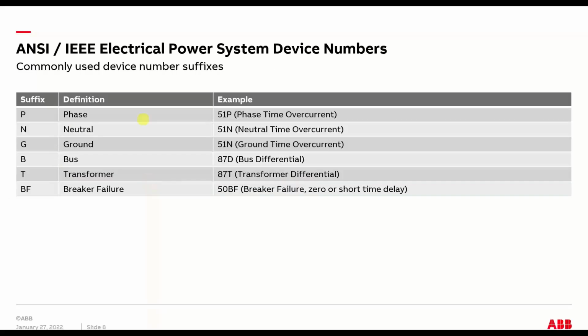Then there's some common suffixes that are used on those devices. P for phase, so you'd have a 51 time overcurrent with a P meaning the phase, N for neutral, G for ground, B for bus. There's a typo here. I should say 87B as in boy. T for transformer, that's 87T, transformer differential. BF would be breaker failure.